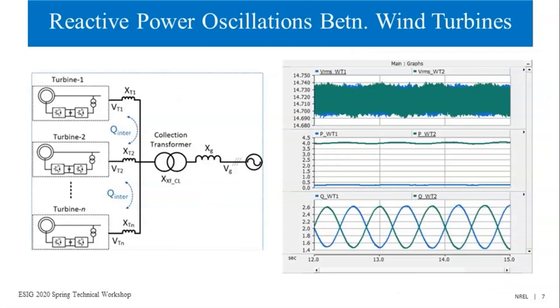Switching gears a little, I'll talk about reactive power oscillations between wind turbines. What you see here are simulations for a wind power plant. The models are basically vendor-supplied models, so they have all the control functions of the wind turbines embedded inside them. We observed reactive power oscillations from turbine to turbine, like two turbines exchanging reactive power as high as 1 megavar.